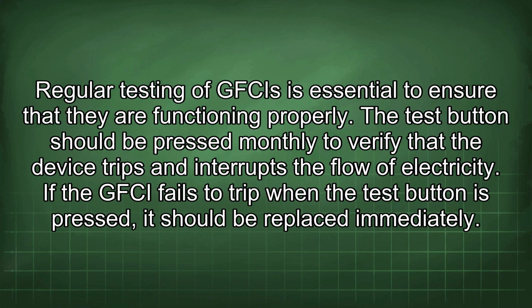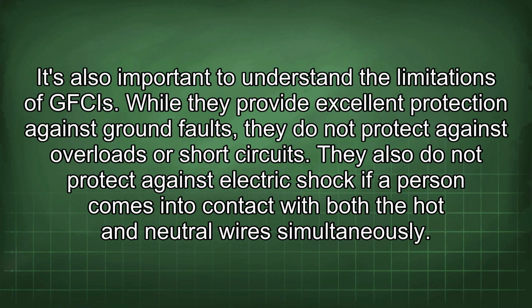Regular testing of GFCIs is essential to ensure that they are functioning properly. The test button should be pressed monthly to verify that the device trips and interrupts the flow of electricity. If the GFCI fails to trip when the test button is pressed, it should be replaced immediately. It's also important to understand the limitations of GFCIs. While they provide excellent protection against ground faults, they do not protect against overloads or short circuits. They also do not protect against electric shock if a person comes into contact with both the hot and neutral wires simultaneously.